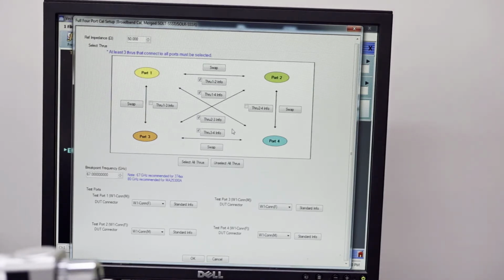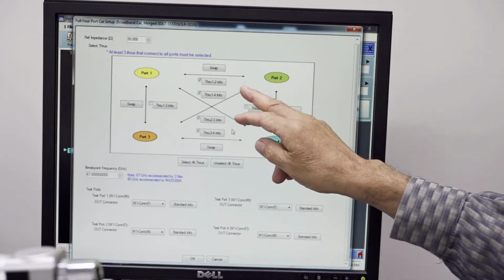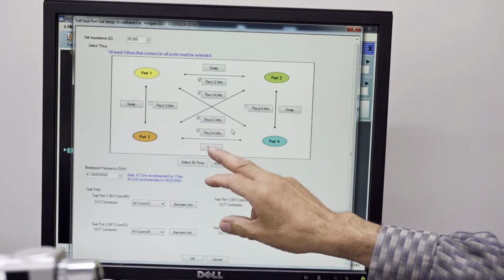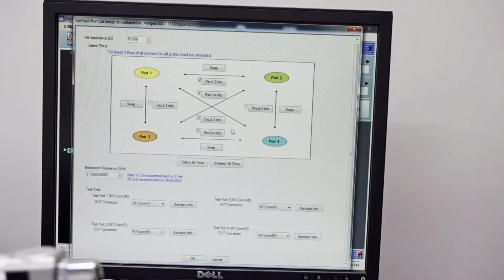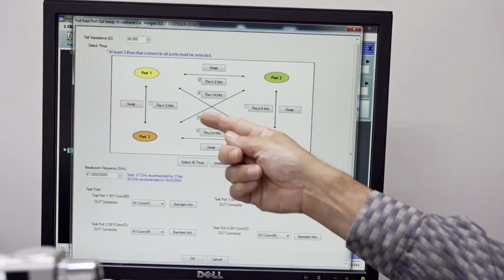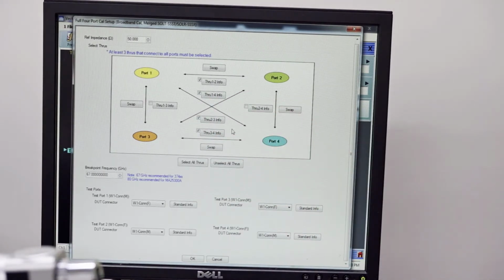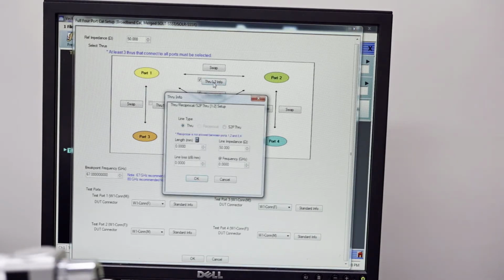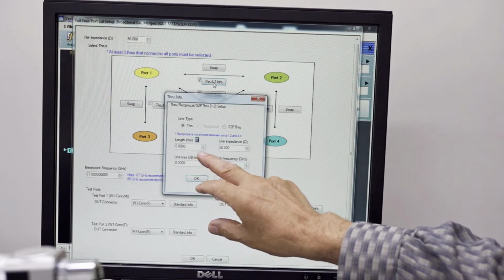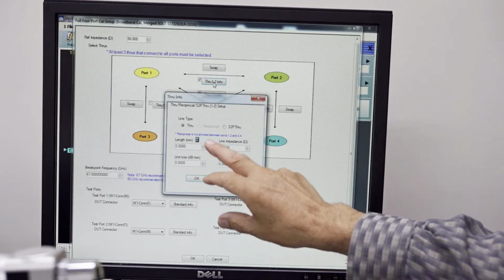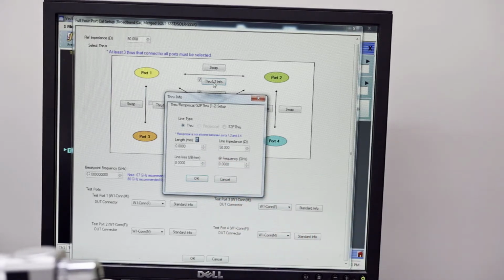For this setup with these modules, we can go through these 4 selections, which is 1 through 2, 1 to 4, 2 to 3, and 3 to 4. And the key is that you need to include all of the ports, at least one selection of each of the ports that are configured and available. And then finally, what we do is define the throughs. And so, for instance, in this configuration, the through 1 to 2, we have it set up as a through with an insertable connection. So I'll show you close up when we get down to the calibration.